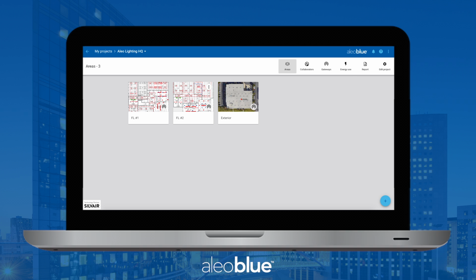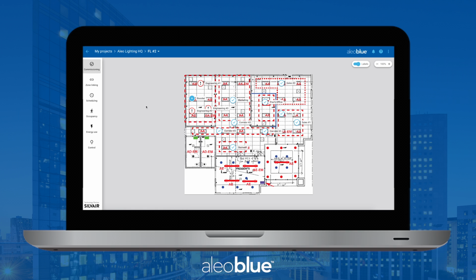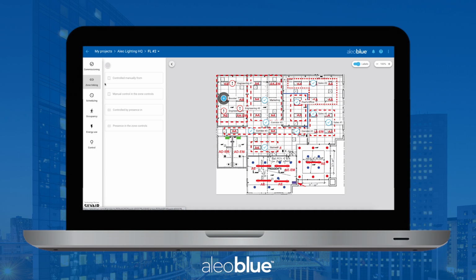To start the zone linking process, open the area you want to work on and click the zone linking icon on the left. Click one of the zones you'd like to link. In this example, we want to link Corridor 1 with Corridor 2, so that any motion detected in Corridor 1 will light up the full corridor.